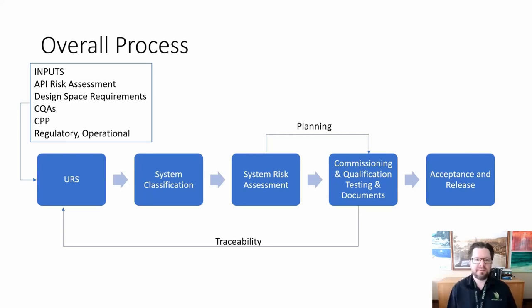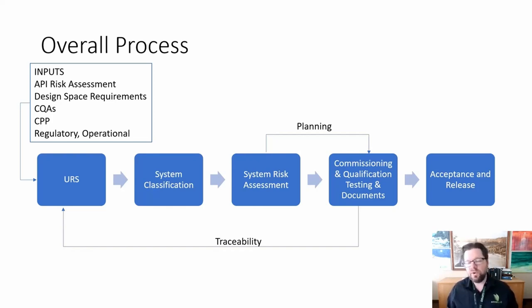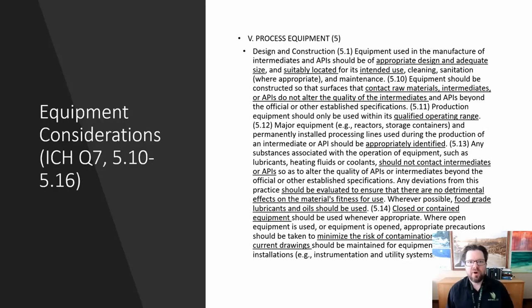You have to develop and demonstrate a scientific rationale for the selection and validation of your equipment and how it relates to your CPPs and CQAs. Obviously you can then go through acceptance and release. One thing that's not in this general flowchart is if you have modifications to the equipment, you need to do a design qualification aspect — add that into this process and then do a design review. This is a very well-known thing and you can do that with your vendor. This is a direct copy and paste from the ICH Q7, sections 5.10 all the way to 5.16.